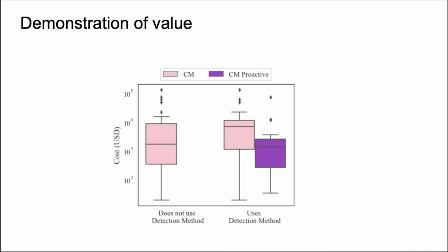Sarah looked at the data for an industrial company running a proactive maintenance program on 10 critical pumps at one plant. Over 2 years, there were 45 total corrective work events evenly distributed between corrective work events that were unanticipated and corrective work events which were generated from an alert from the predictive models.